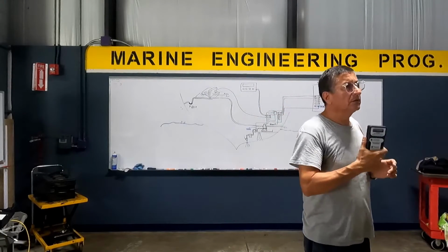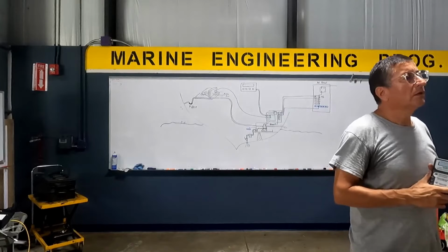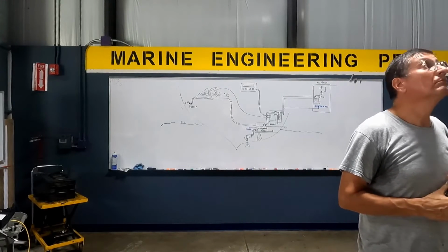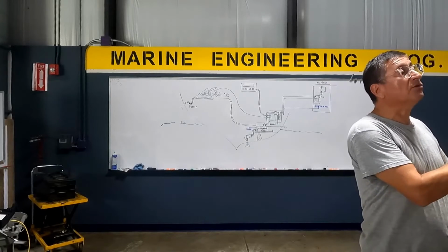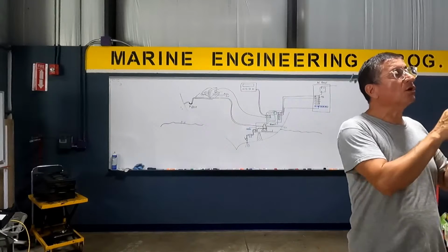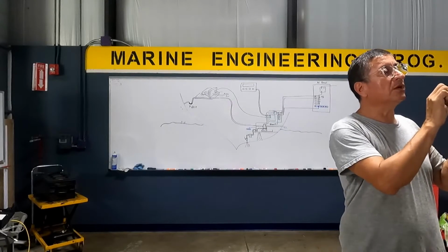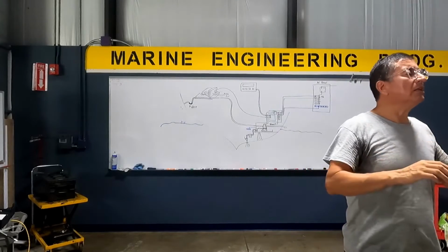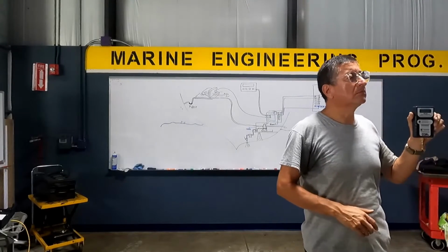Yeah, I was just making sure that you said more microns, more humidity. If you have 2000 microns here, you have a lot of humidity. When the pump starts to work, the micron will be reducing to around 500. When it's around 500, you can disconnect the pump. All right, so that's the pump.